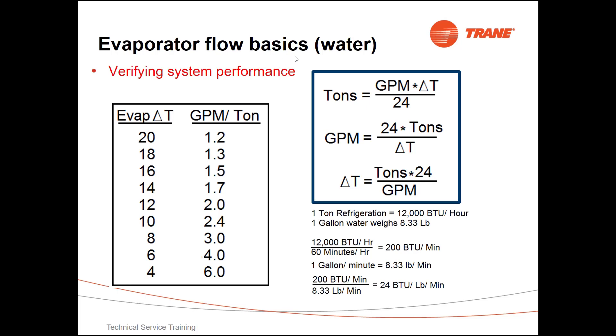So for our evaporator flow basics, we're concerning water here — we're not talking about glycol — but the delta T that you will get from your evaporator is actually in correlation to how many gallons per minute per ton that you have flowing through your machine.